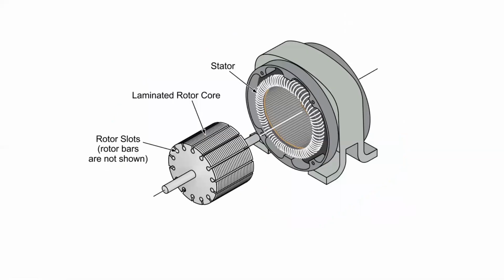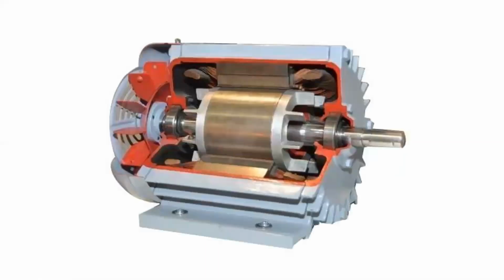The stator is what produces the electromagnetic flux in order to turn the rotor. The rotor bars here and the squirrel cage, which is not shown, sit in the middle of the stator with a very small air gap, or very small tolerance, permitted between the stator and the rotor. It looks like this if we were to cut it apart.